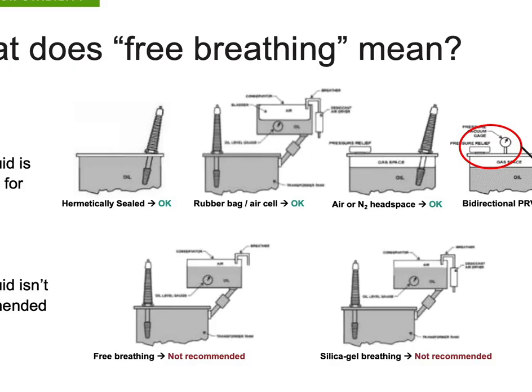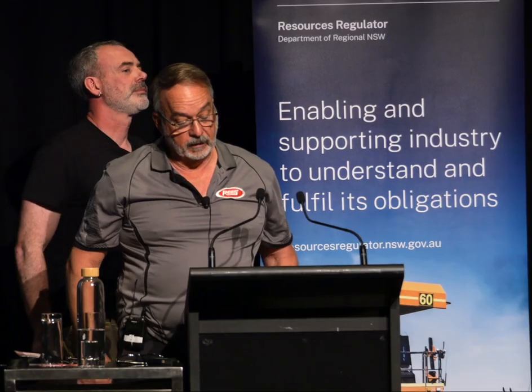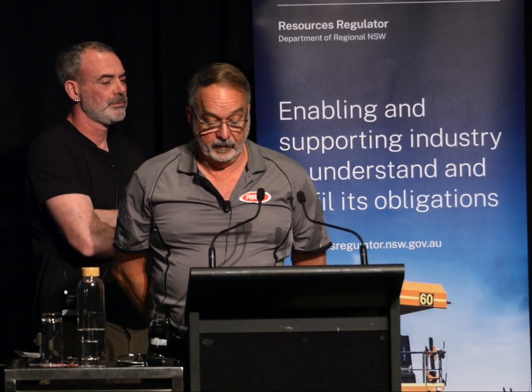There are a number of different scenarios. We've just taken out one, and that was for a pad-mounted network or substation transformer as far as retrofilling, from 500 kVA through to 7,500 kVA. Step one was to adhere to all required safety precautions, codes and regulations.